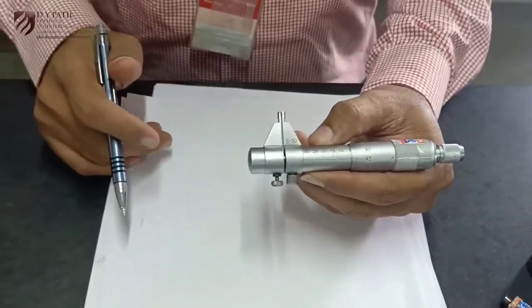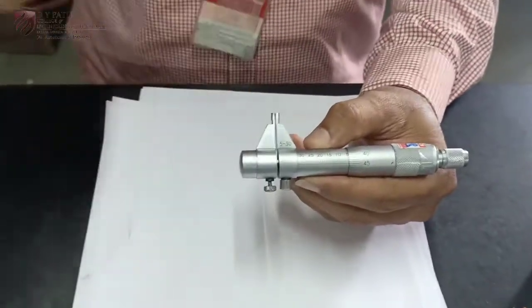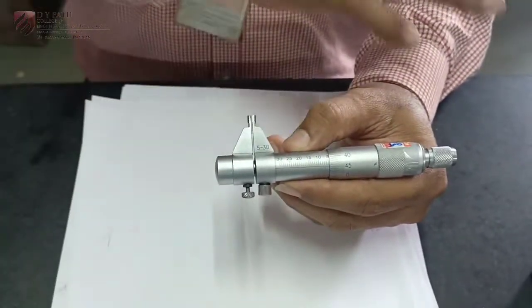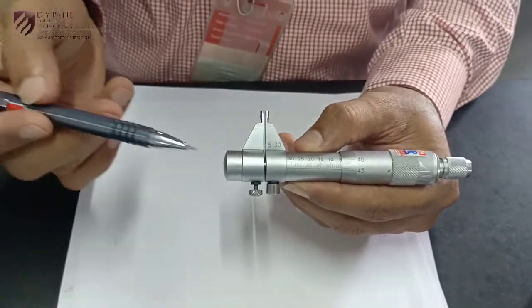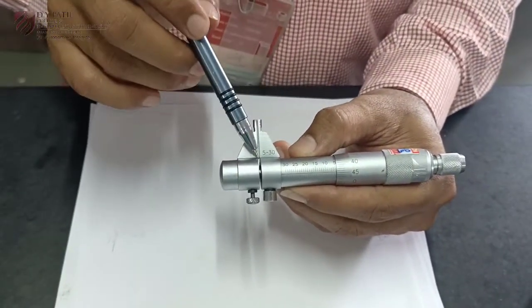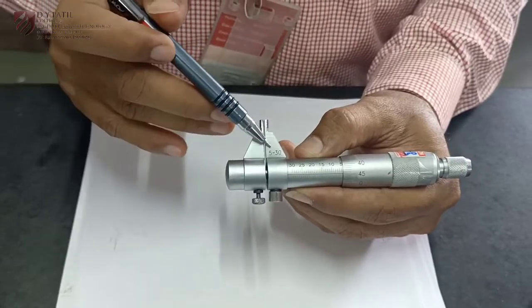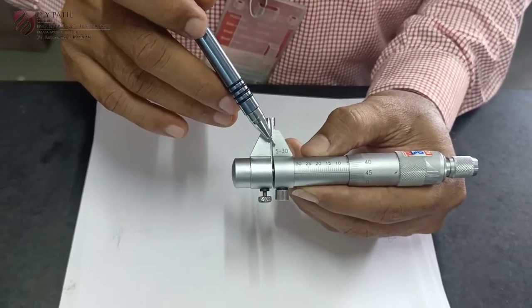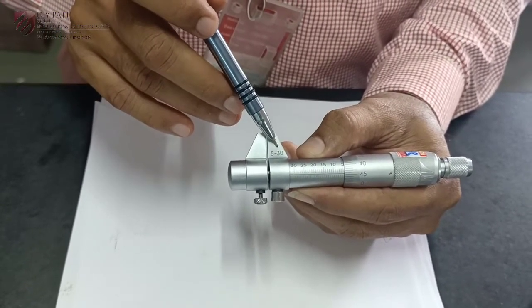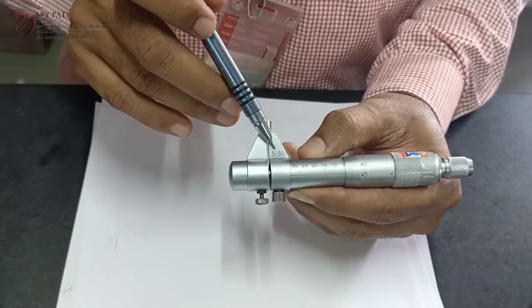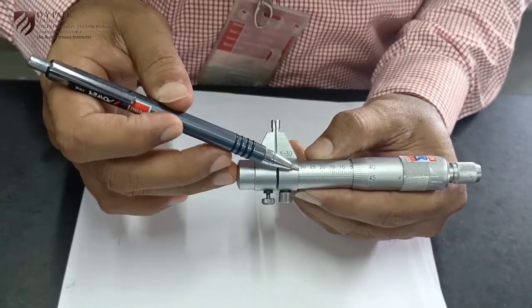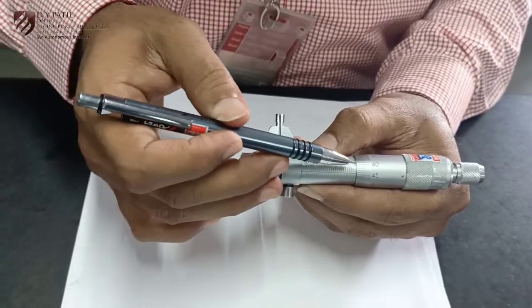In case of inside and depth micrometer, the scales are exactly opposite to that of outside micrometer. For example, if you see here, this is the first range of inside micrometer which starts with 5 to 30. The span is 25 only. It starts with 30 and it ends at 5.